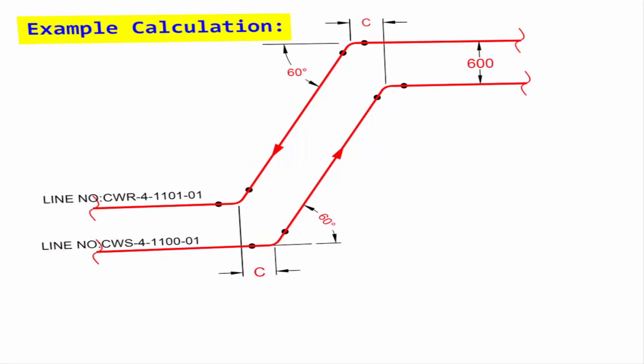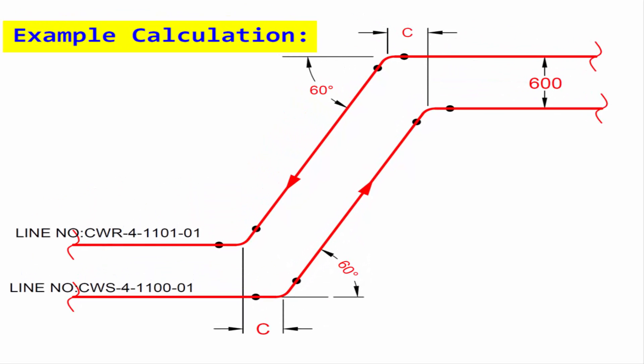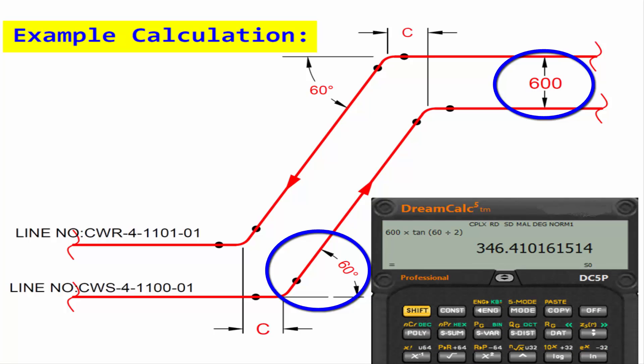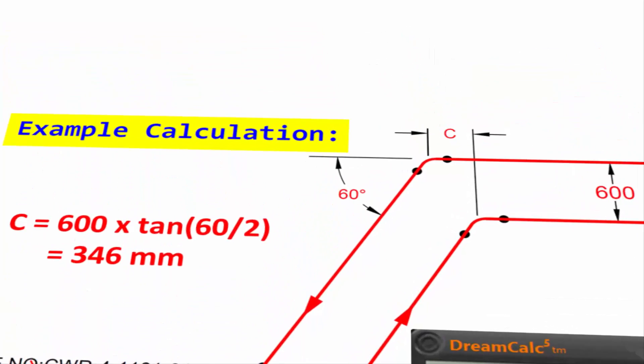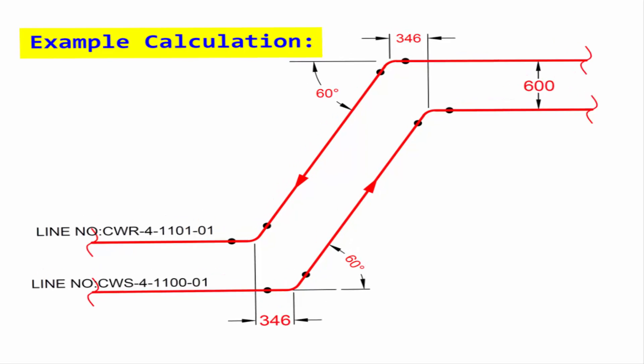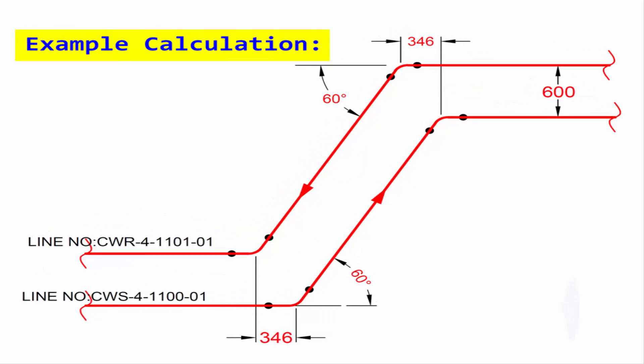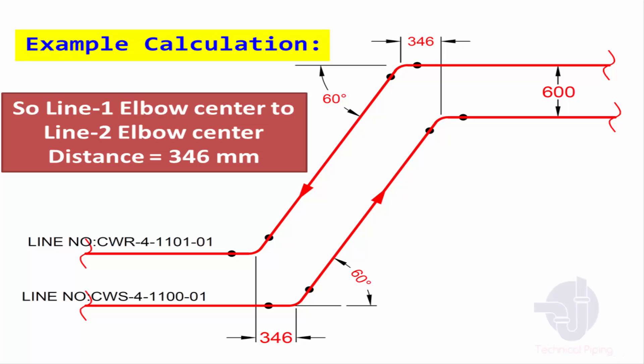Example calculation: In the given isometric drawing, spread distance is 600 millimeters and rolled elbow degree is 60 degrees. Enter the values in scientific calculator. So line one elbow center to line two elbow center distance is 346 millimeters.